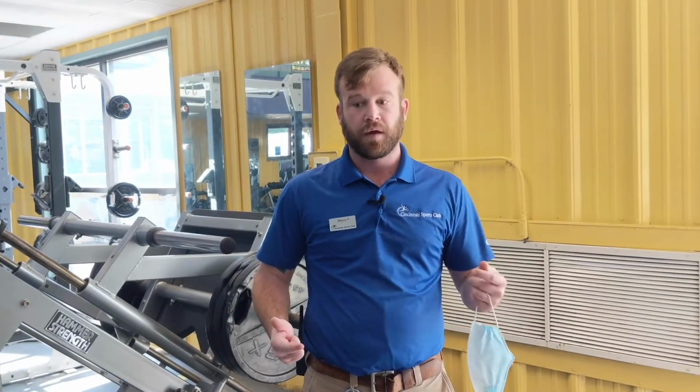In February, before it was officially labeled a global pandemic and it hadn't really hit the States yet, we decided to open our fresh air dampers to 50% in accordance with our already existing pandemic plan. What this means is that instead of every 6 minutes, all the air in the club is being exchanged with fresh air every 1.5 to 3 minutes.